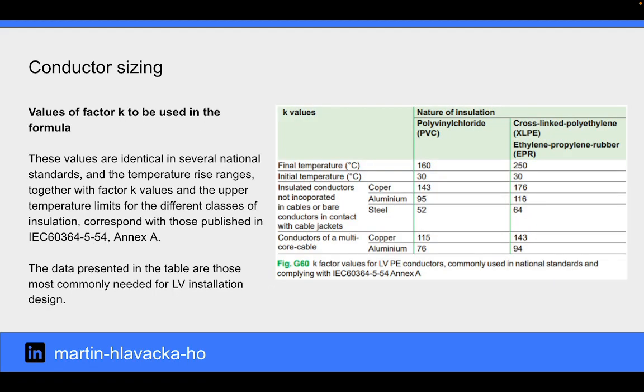Values of factor K to be used in the formula. These values are identical in several national standards, and the temperature rise ranges, together with factor K values and the upper temperature limits for the different classes of insulation, correspond with those published in IEC 60364-5-54 Annex A. The data presented in the table are those most commonly needed for LV installation design.